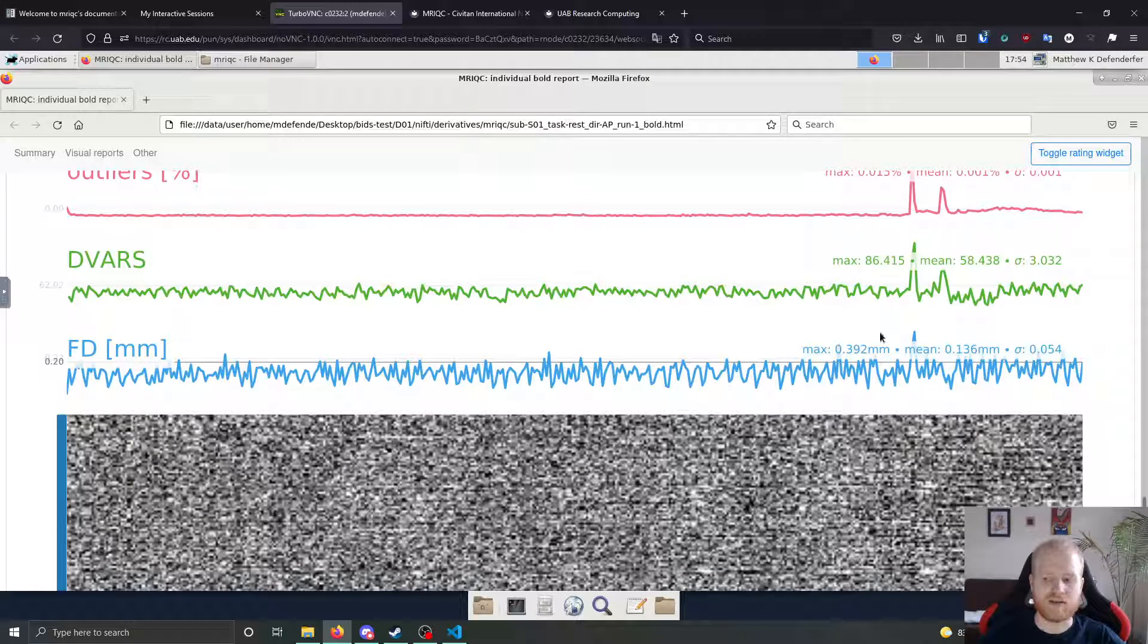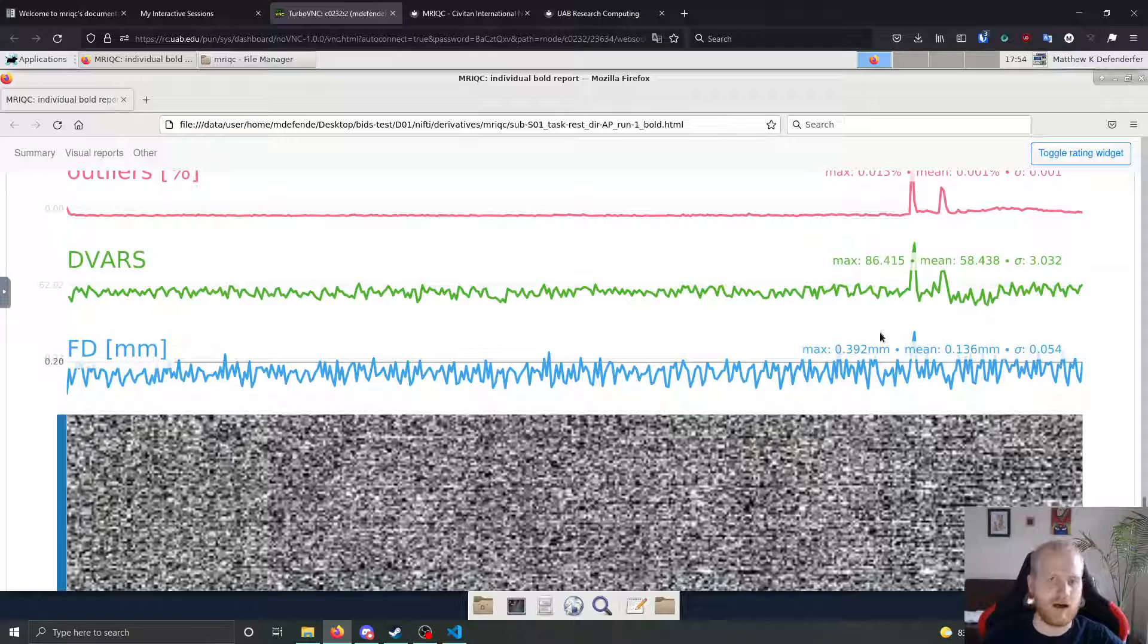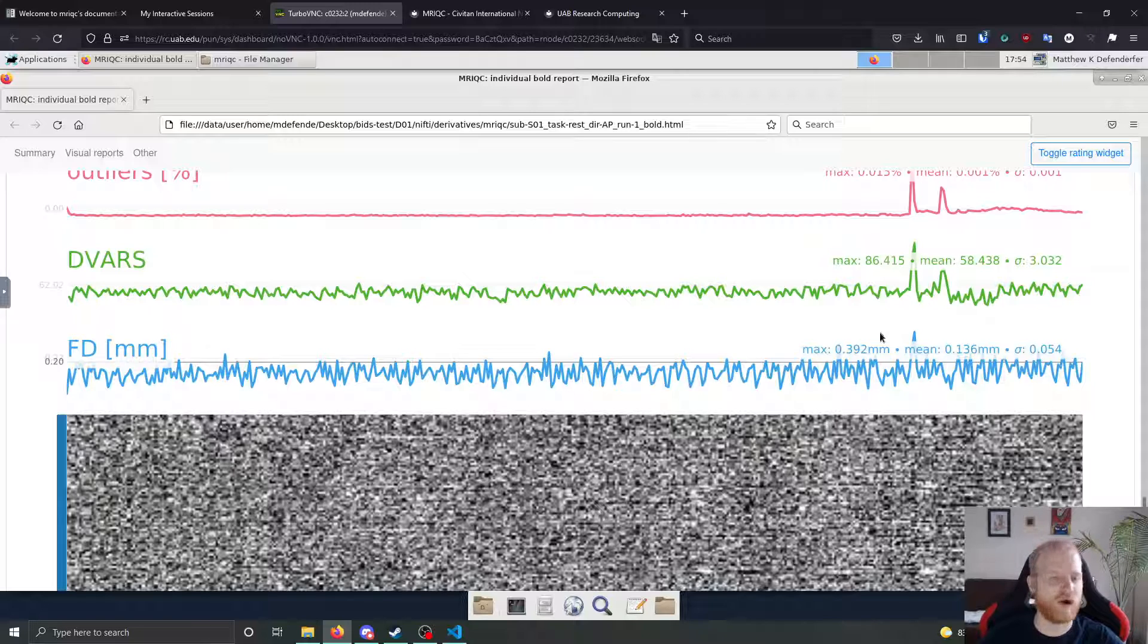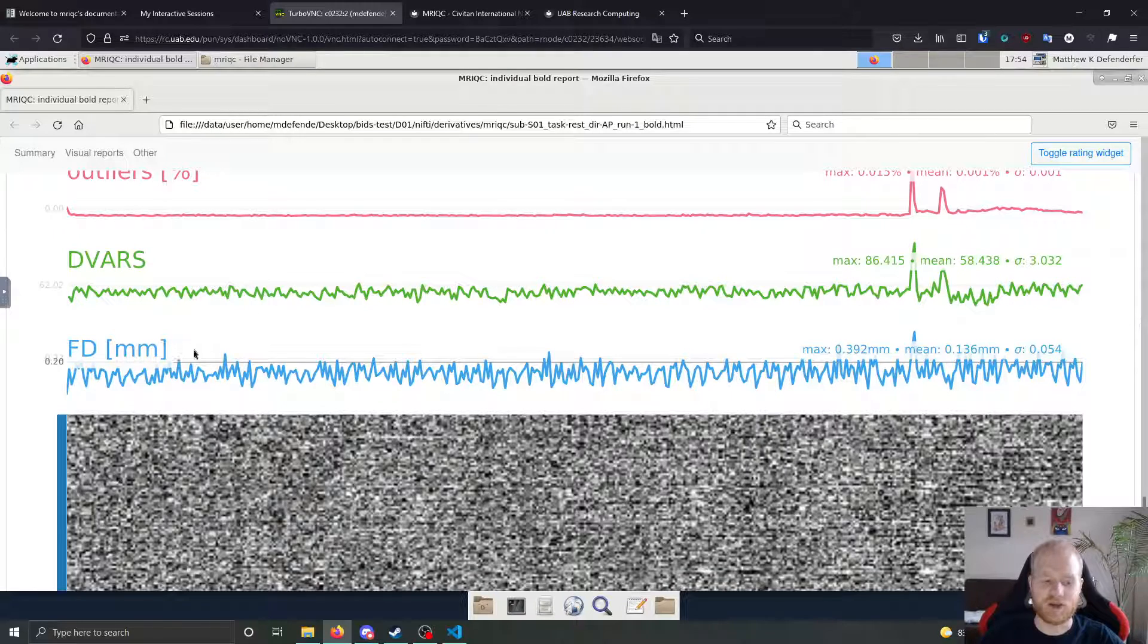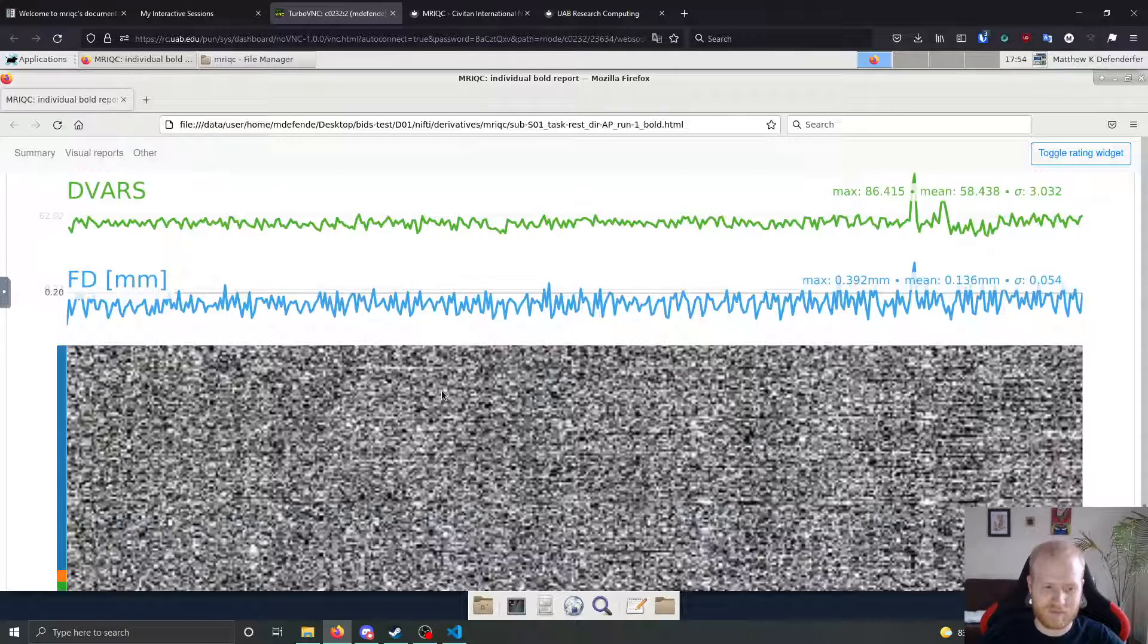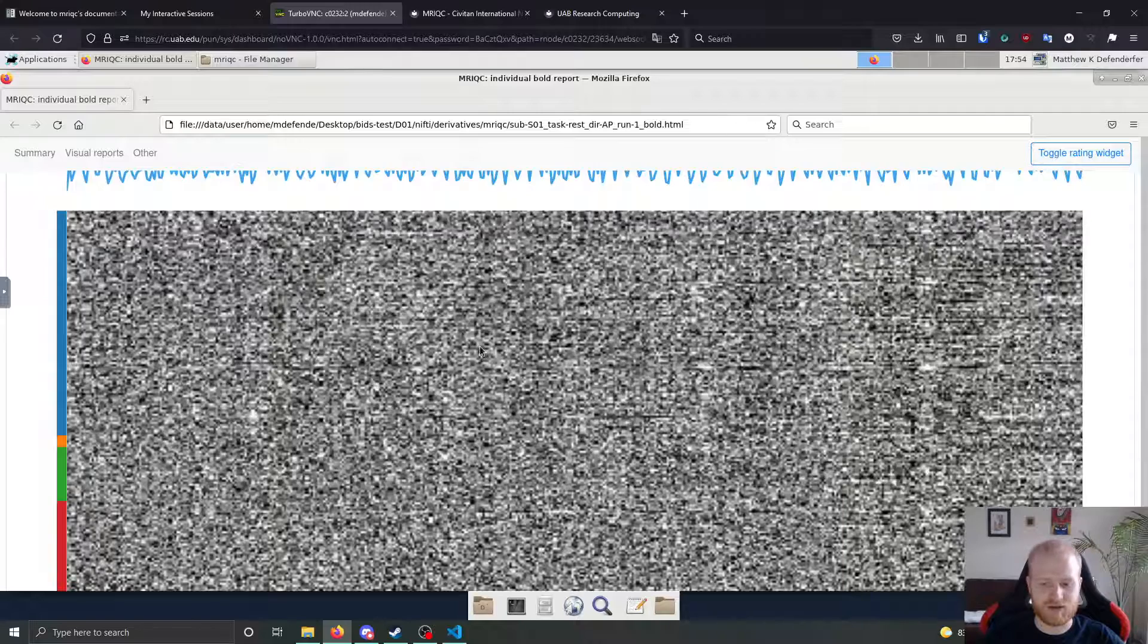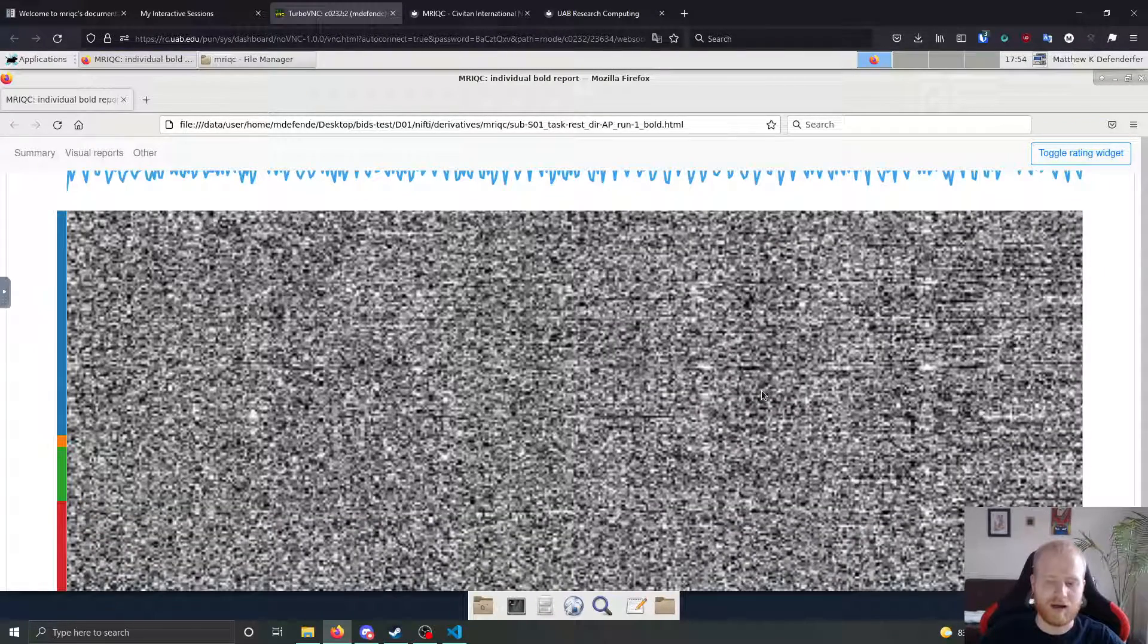Just to be clear though, no actual motion correction is saved to your data. All your data is still gonna be raw data at the end. So you'll still need to perform motion correction and no volumes are scrubbed from the data if they pass this 0.2 millimeter threshold or anything. This is just purely information for you to see how many images there might have been that went to or past this cutoff point.